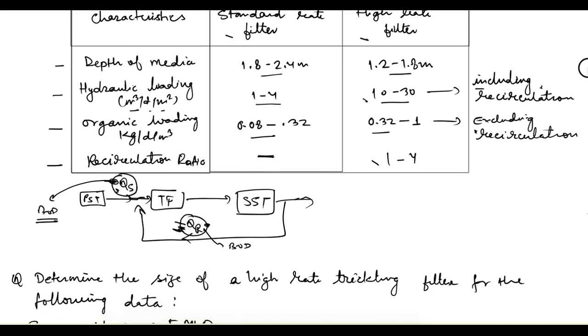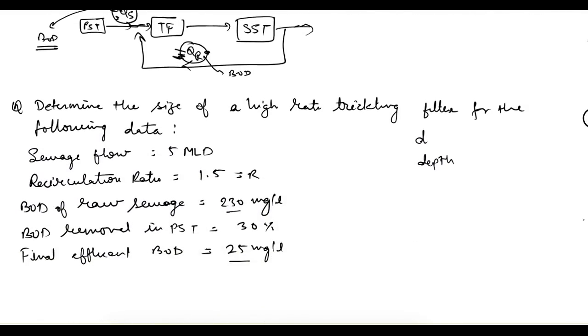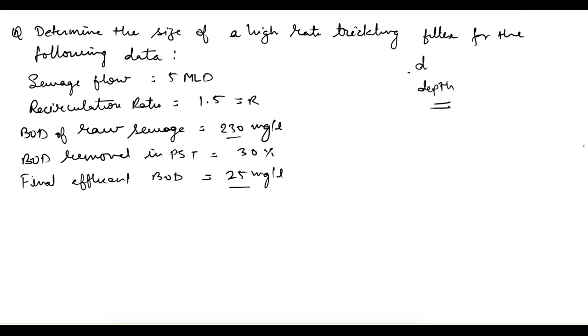Now let's see Problem 1: determine the size of a high rate trickling filter for the following data. Sewage flow is 5 MLD, recirculation ratio R = 1.5, BOD of raw sewage is 230 mg/L, BOD removal in PST is 30%, and final effluent BOD desired is 25 mg/L. We need to find the diameter and depth. We can assume the depth from the known range, and find the area and volume using the NRC efficiency formula.